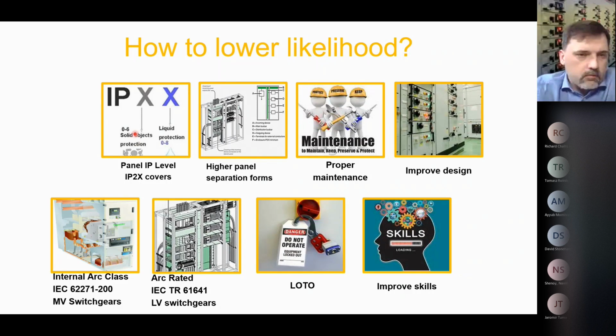Panel IP level, which is ingress protection. We try to keep at least the level IP2X for internal protection. I will show you an example on this. Higher panel separation forms. This is internal separation form of panel, and I will discuss in detail what it is. Proper maintenance, of course. I think recently there was a publication in the UK about how important it is to properly maintain your medium voltage breakers to avoid catastrophic accidents. So yeah, that's important. I would say maintenance. Please do it.